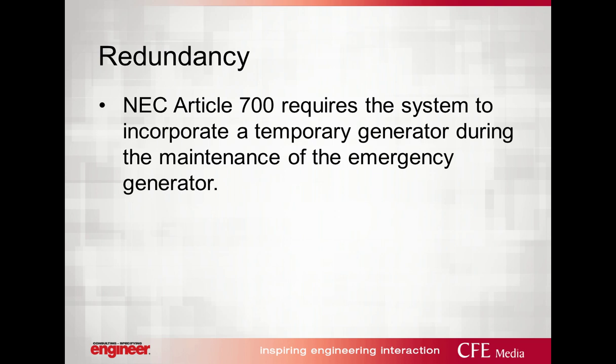So if I have an emergency generator distribution system and for some reason or another, I need to maintain a switch that's in that system, well, I don't want to take that system down completely. So I might have the capability of wrapping into a 701 system for a short period of time or into another 700 system that brings me power for a temporary period of time within my distribution system to keep it active.